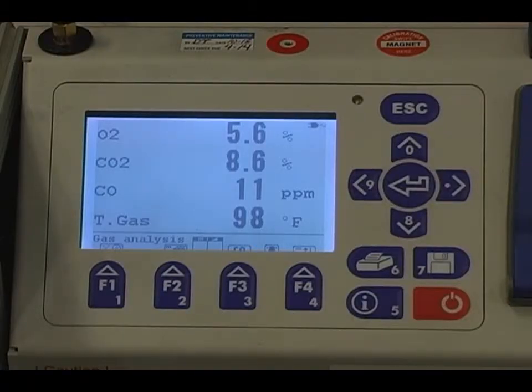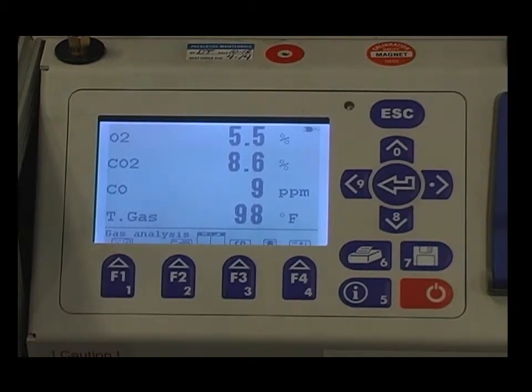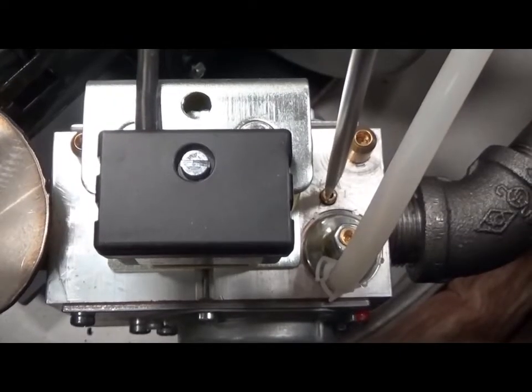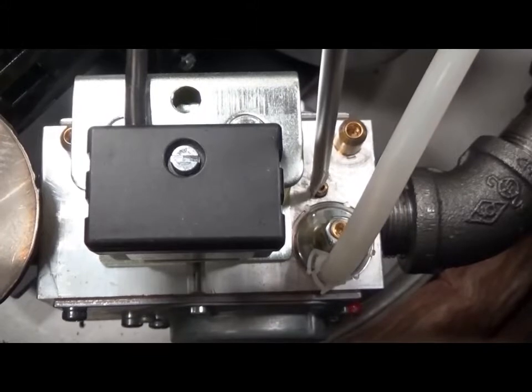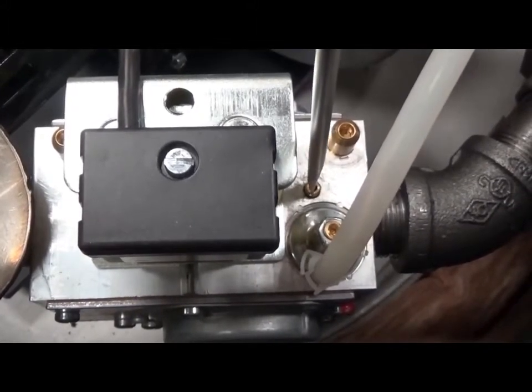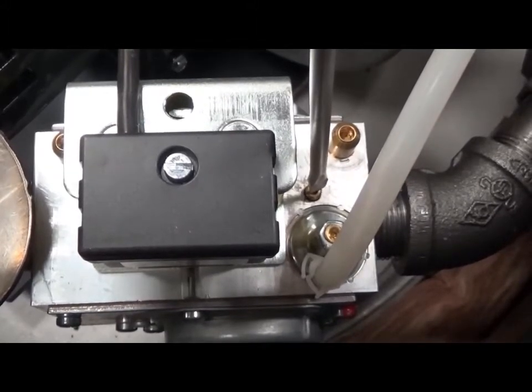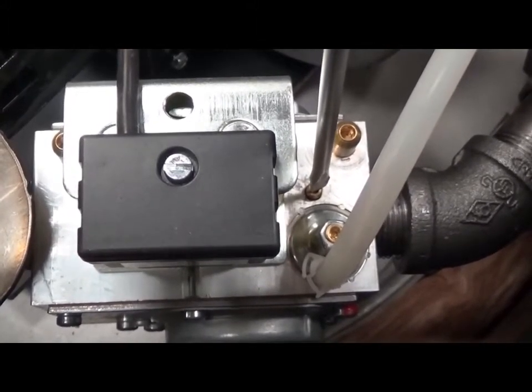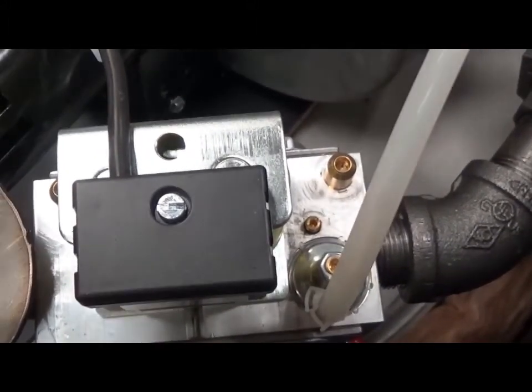With the burner firing, measure the flue gas with the combustion analyzer. The carbon dioxide level, CO2, must be between 8.5% and 9.5% for natural gas and between 9.5% and 10.5% for propane gas. If the level is in this range, no adjustment is required or recommended. If the level must be adjusted, this is done by turning the slotted brass gas valve orifice screw counterclockwise to increase gas flow and increase CO2, or clockwise to decrease gas flow and decrease CO2. See gas train illustrations in the installation and maintenance manual supplied with the product. If at any point carbon monoxide is in excess of 200 parts per million, contact PVI Customer Care for assistance.